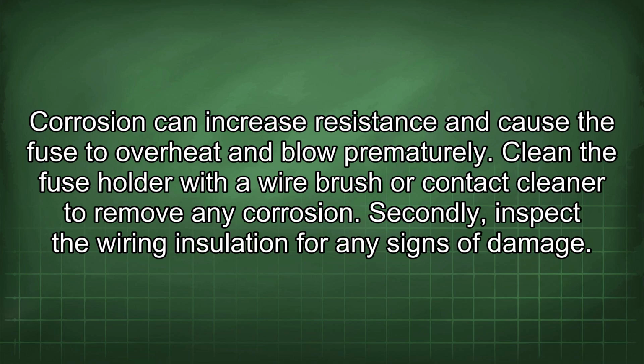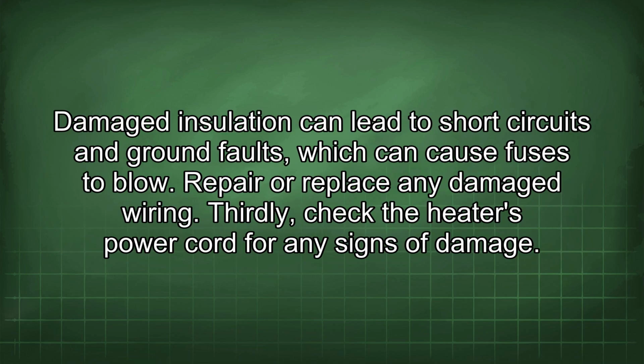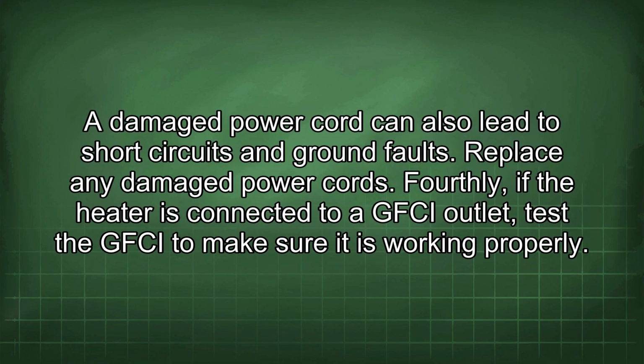Secondly, inspect the wiring insulation for any signs of damage. Damaged insulation can lead to short circuits and ground faults, which can cause fuses to blow. Repair or replace any damaged wiring. Thirdly, check the heater's power cord for any signs of damage. A damaged power cord can also lead to short circuits and ground faults. Replace any damaged power cords.